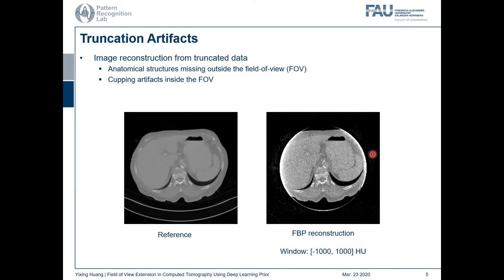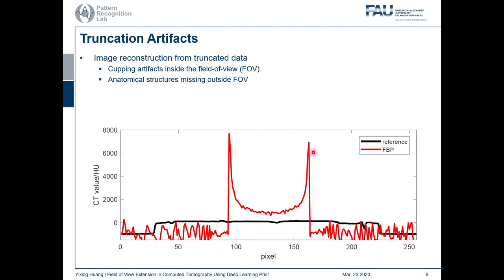Image reconstruction from truncated data directly with the standard filtered back projection method will suffer from artifacts. Here this is one reference image, and this is its FBP reconstruction from truncated data. We can see the anatomical structures outside the field of view boundary are entirely missing. In addition, the structures inside the FOV boundary have much brighter values. If we plot a line, we can see its intensities look like a cup — that is why these brightness artifacts are called cupping artifacts.